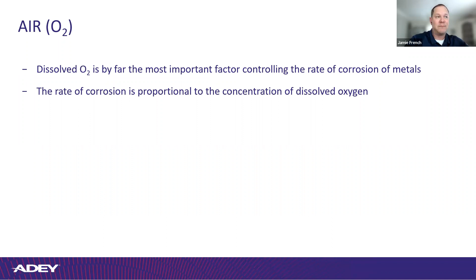But oxygen is the main factor for corrosion, and it's proportional: the amount of dissolved oxygen is how much corrosion you're going to get. Again, picking on steel here because it's ferrous. With lower concentrations of oxygen, with no inhibitor, you get the corrosion that forms magnetite. If you have oxygen in your system that exceeds the rate at which you can remove it, you typically have hematite occurring, and that can cause pitting, perforation in the steel surface, and leaks. Again, making up more water, introducing more oxygen, so it's a compounding issue.